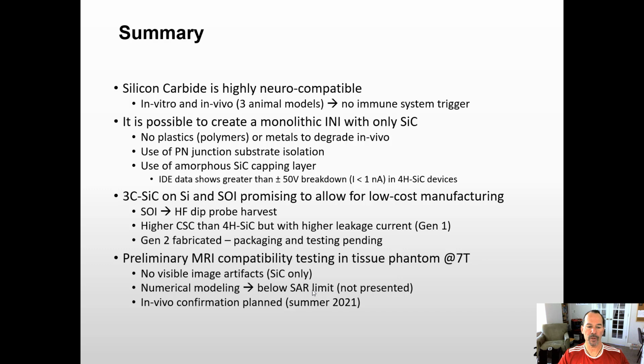No image artifacts. What I didn't show due to time is we did numerical simulations that showed that we're below the specific absorption rate limit by the FDA. We're below that limit for cubic silicon carbide. Other materials such as titanium and so on are not. And our in vivo confirmation of this is planned for this summer if everything works out well with the pandemic.